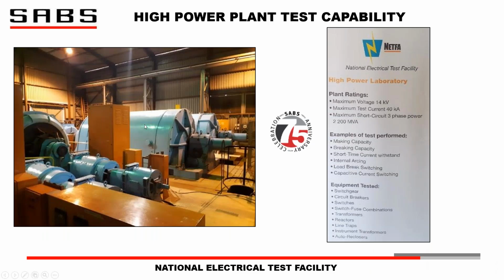Okay, in order to introduce what the power plant is, as I mentioned, it supplies very high fault currents and high power fault currents into devices under test. This is a photo of the banner where you enter NETFA, well, the high power lab. Remember, there's two other labs, and I'm only going to mention these three parameters here. The maximum voltage is 14,000 volts, the maximum test current is 40 kA, and the maximum short circuit three-phase power is 2,200 MVA. So it's a powerful plant. There will be material circulated about the plant. There's stuff later in the presentation about the more detailed capabilities, and you're welcome to ask Lucas or Seth at the end of the presentation any questions about the capabilities. A lot of you listening in or watching in will be aware of the capabilities.